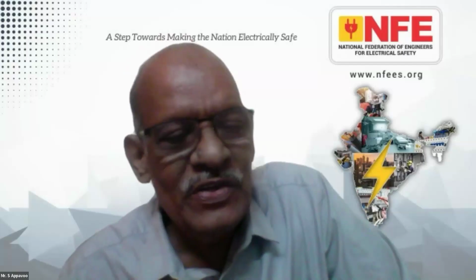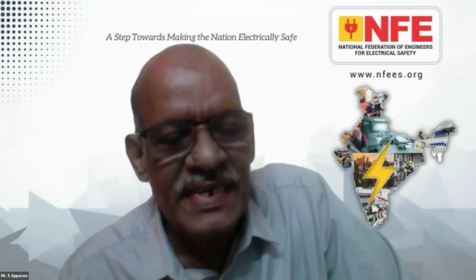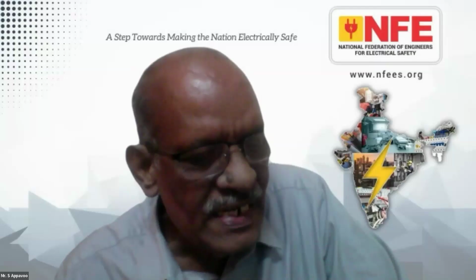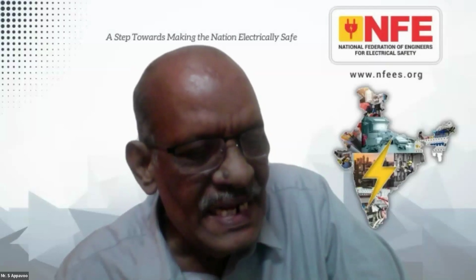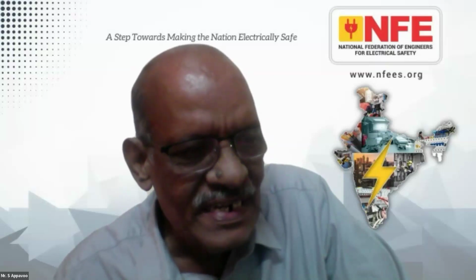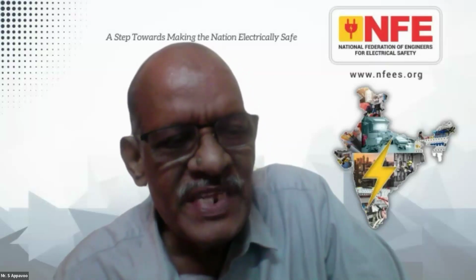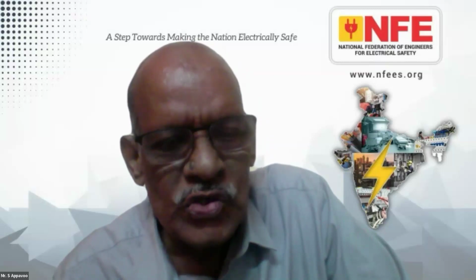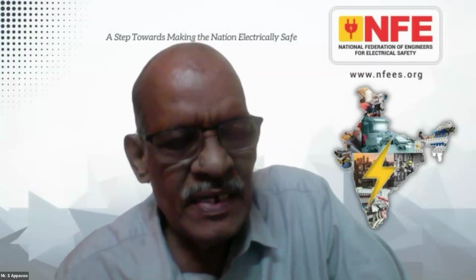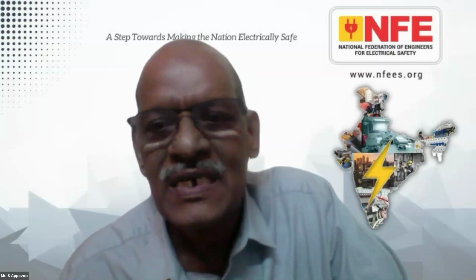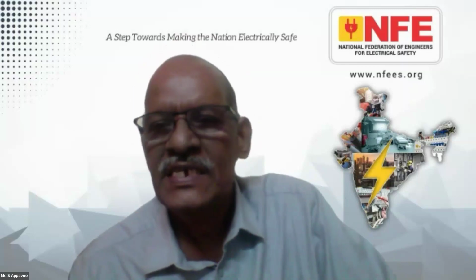Mr. Radhasamy, you should have your power quality analysis study done and see whether the control systems are getting affected due to the radiation, meaning conducted or radiated emission from these harmonics, whether they are closer by. For example, a PLC panel could be closer to your VFD panel, something like that. You check with the harmonics analyzing people.